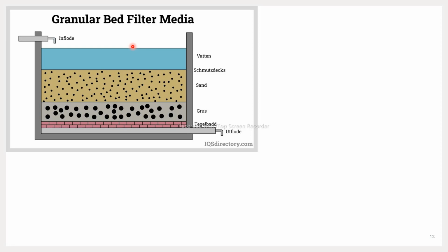Now what happens is that above the sand there will be a layer of deposits. As in the earlier MCQ, it was told that as the time increases, the deposits also get increased, and as the deposit gets increased, more effort will be needed to pass the water through the media. So that means the pressure drop or head loss also increases.